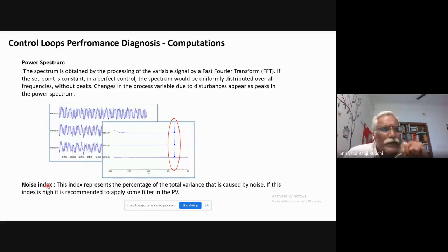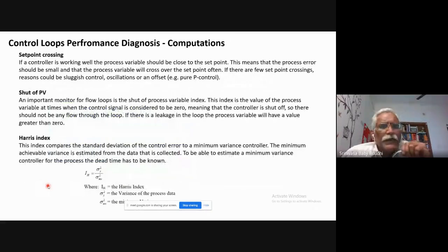Then another thing which we calculate is the set point crossing. How many times the process variable is crossing the set point. Typically, if the control is proper, then you will see that the process variable will be very close to the set point, making some crossings occasionally. Okay. If there are very few crossings of the set point by the process variable, then it indicates that there is sluggish control. Okay.